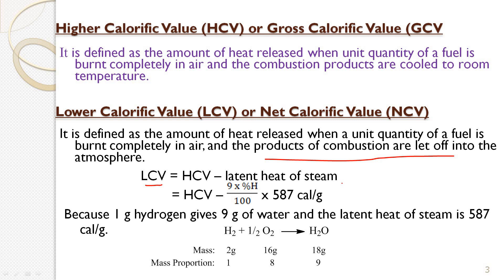The latent heat of steam is 587 calories per gram, or 587 kilocalories per kg. Since one part of hydrogen by mass produces 9 parts of water, we write: LCV = HCV − (9 × percentage of hydrogen / 100) × 587 calories per gram. Here, 9 represents the 9 parts of water produced for one part of hydrogen, which is why we multiply the hydrogen percentage by 9 divided by 100.